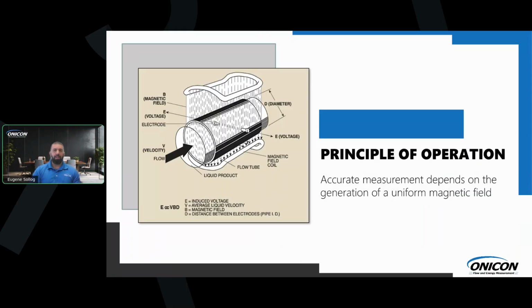Taking a look at this cross-sectional cutout of what the meter actually looks like, there's a large coil on the top and a large coil on the bottom of our flow meter, and two giant stainless steel electrodes on each side. So we're able to create a very large, very uniform magnetic field through the whole cross-sectional area of the flow tube. If you look at the diagram, you can see big 316 stainless steel electrodes. We have a 316 stainless steel flow tube.